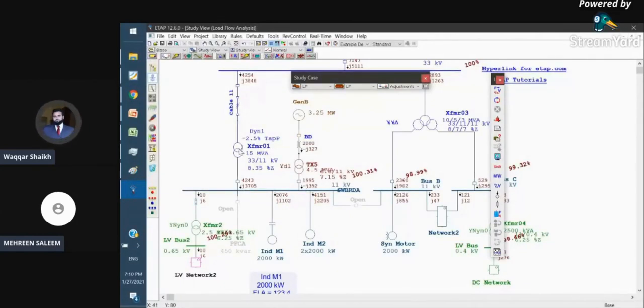So here comes the engineering judgment that you should not select a transformer with much more capacity than your requirements. Normally there are growth factors and demand calculations which enable you to size transformers properly, considering the transformer kVA rating. ETAP will not indicate oversizing of an equipment, it will only indicate undersizing.